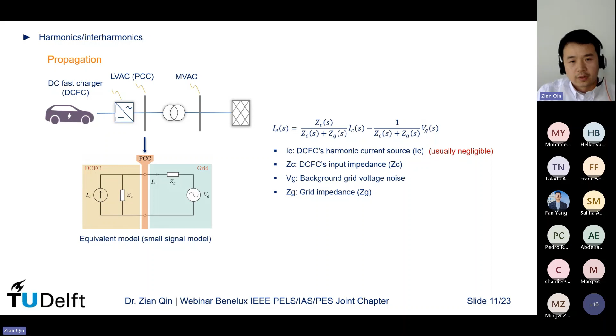It will be affected by this voltage source, which is the background noise of the grid, the grid impedance, the charger impedance, and also the harmonic emission of the charger. So it's a total effect of all these 4 parameters. However, if you think about it, the harmonic emission of the charger shouldn't be a problem, right? Because before the charger is allowed to be connected to the grid, it has to pass certification. In that certification, the harmonic emission will be tested to make sure it is below the limit stated in the standard. So if there is a harmonic or interharmonic problem at the PCC point, it shouldn't be the reason of this harmonic emission.